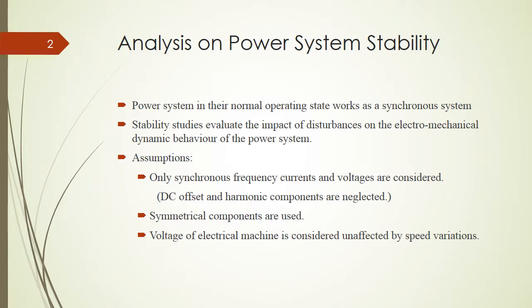Hence, our stability studies need to evaluate the impact of those disturbances on the electromechanical dynamic behavior of the power system. To be able to do that, we need to simplify our system by making assumptions. There are three major assumptions: first, only synchronous frequency currents, voltages are considered, so DC offset and harmonic components are neglected. Second, only symmetrical components are used. Third, voltage of electrical machines is considered unaffected by speed variation, so during our analysis we assume that it stays constant.